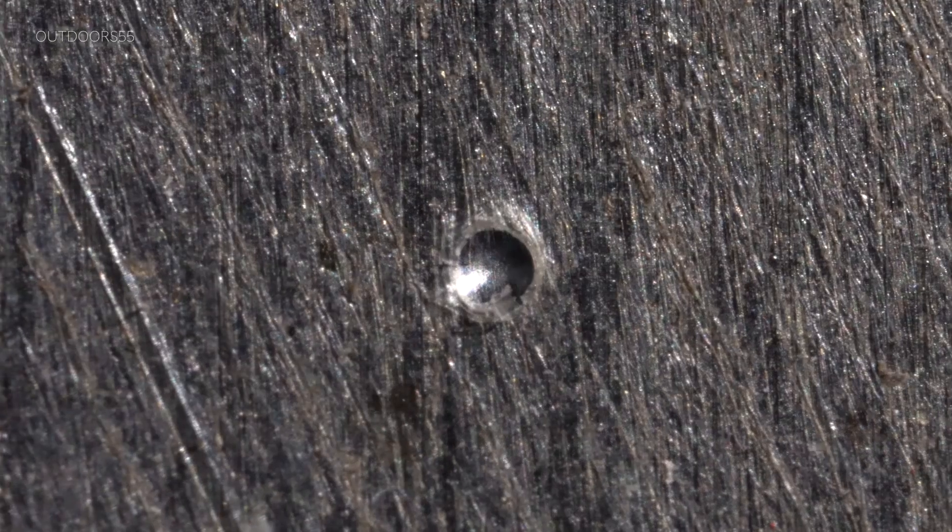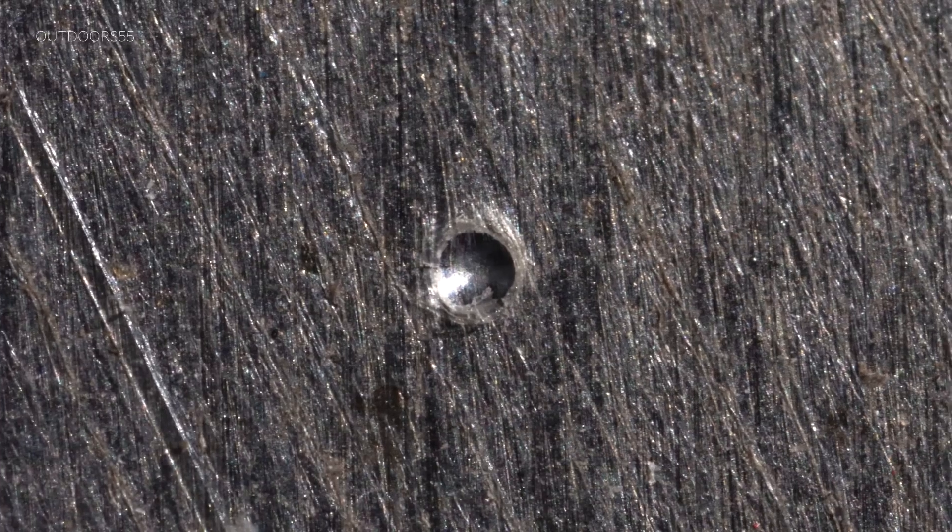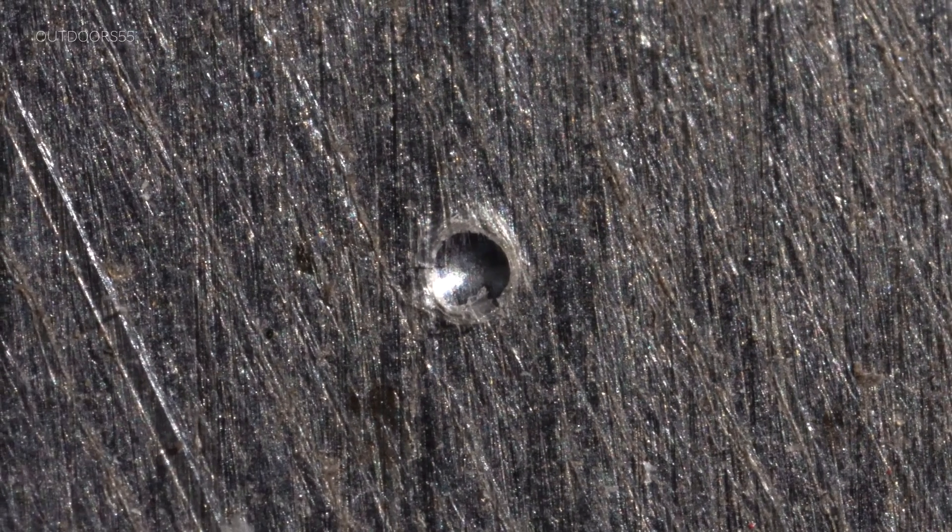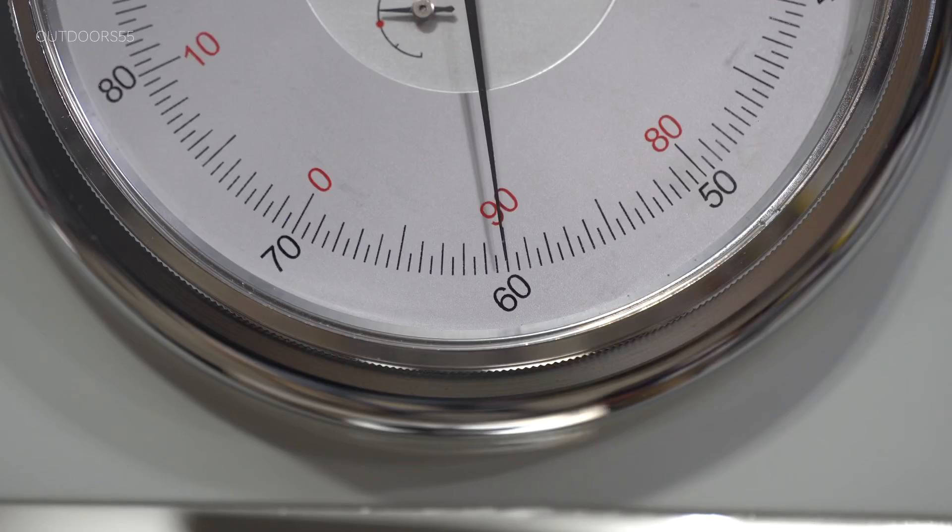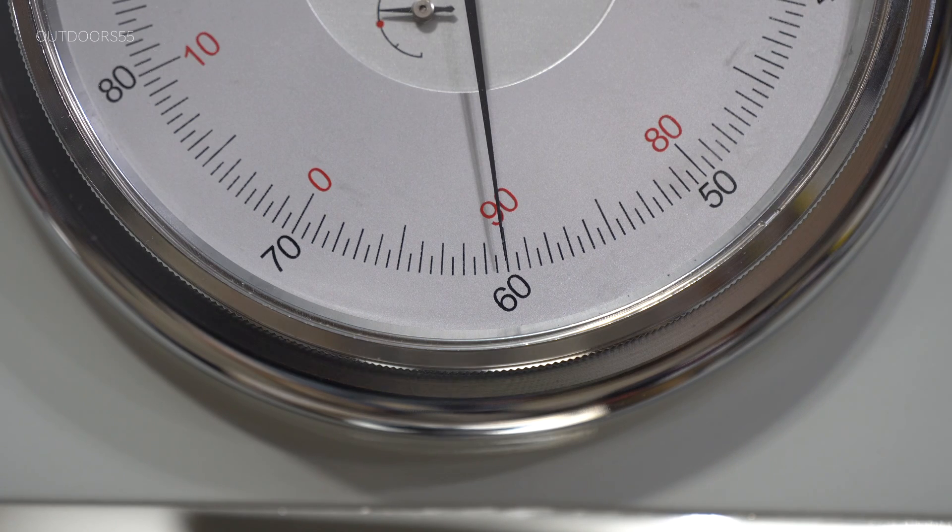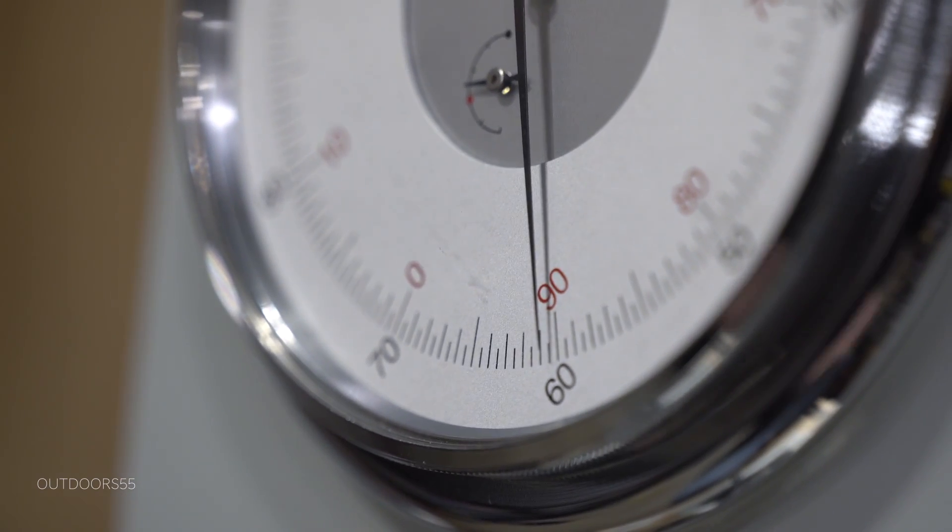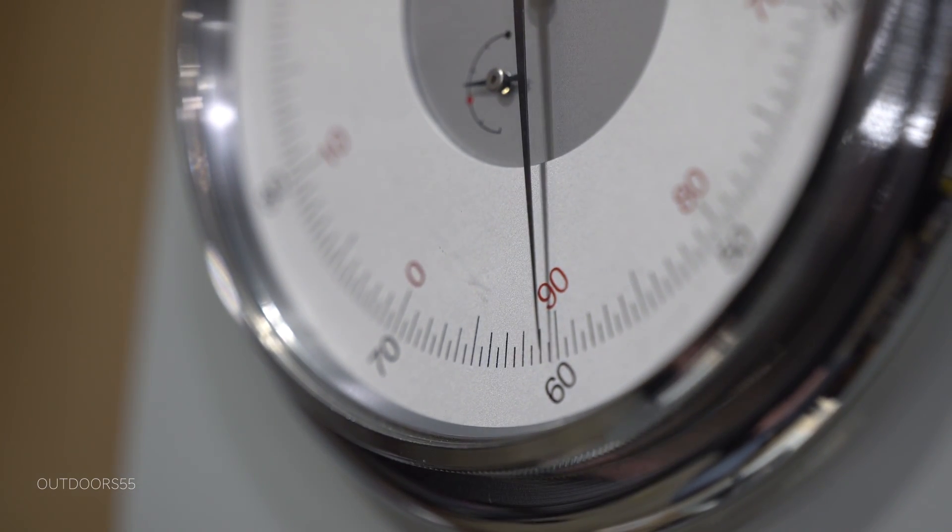And here's the small dimple the penetrator leaves behind. Looks like our first test was 60. I ran this test five times and all of those tests were exactly 60.